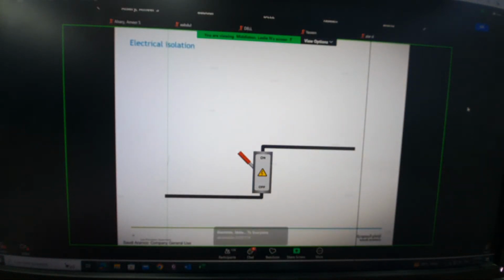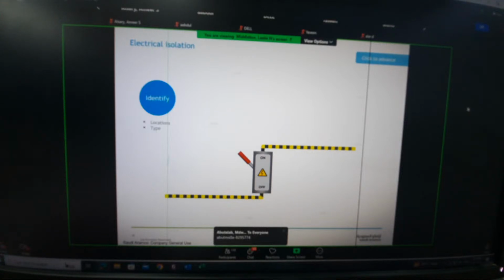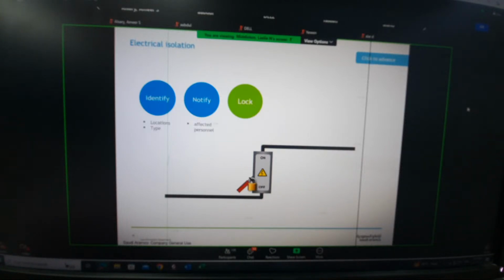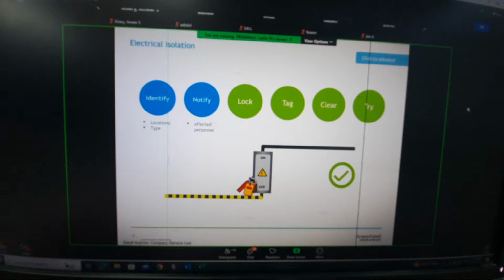So just go through the basic diagram. You must identify locations and types of isolation devices required to isolate equipment. All affected personnel must be notified of the isolation. Close energy isolating devices and lock them out. Tag the locks and maintain a record of isolations. Clear the work area of equipment and personnel. Try to start the de-energized equipment to verify isolation is successful. Remember, the Saudi Aramco electrical isolation process has four key steps: lock, tag, clear, try.